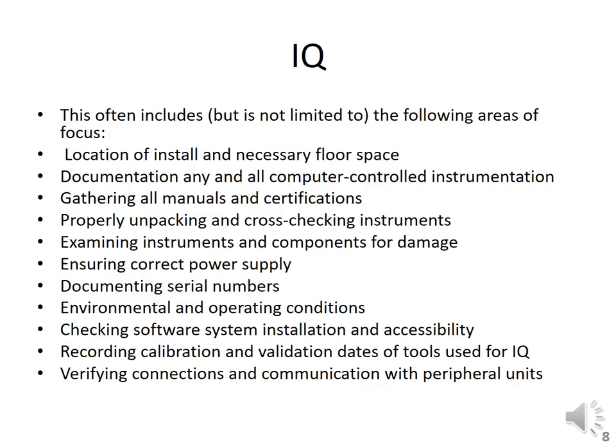Second point, documentation of any and all computer controlled instruments. Now, here the point is that if your machine is equipped with or helped by any other computer controlled instrumentation or instrument, what you have to do is keep the documentation about your equipment and about all the related computer controlled instruments and equipment which are helping this machine.